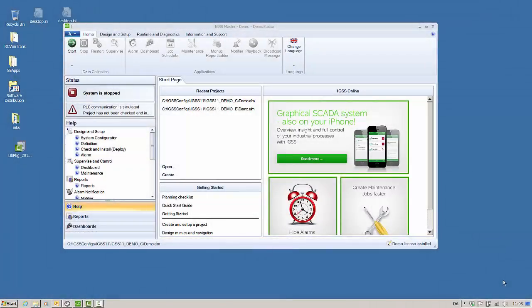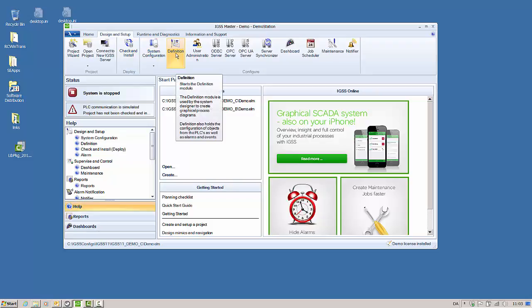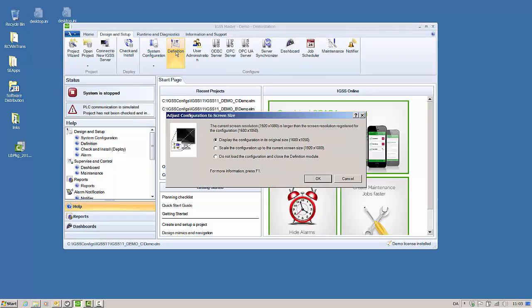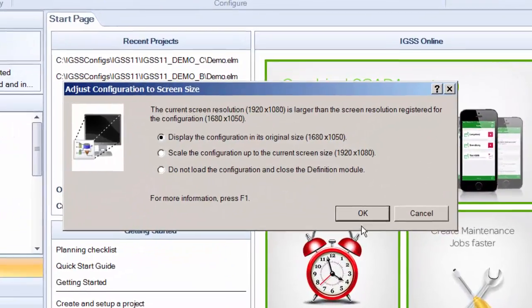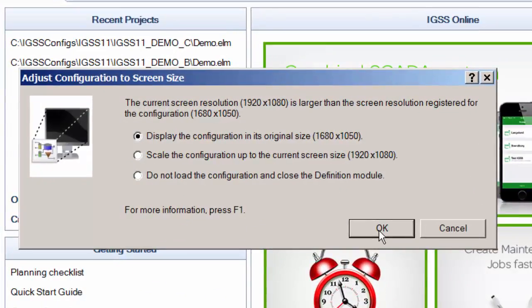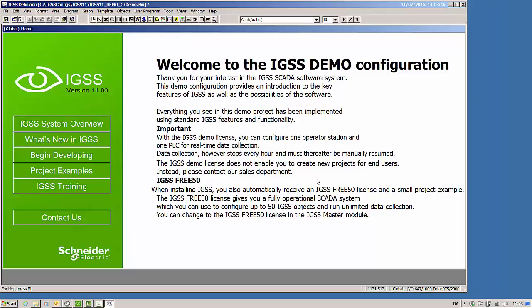IGSS 11 has introduced a new way of scaling configurations when opening them in the definition module. Previously, the system attempted to automatically scale a configuration that was loaded, sometimes with very frustrating results. Now, the system designer will receive a prompt box informing them of a scaling conflict and requesting input about what to do with the configuration. If the resolution of the configuration is different from the present screen resolution, the system designer will be prompted to either close the configuration or rescale it. If the configuration is smaller than the screen, the system designer can load the configuration in its original size, keeping the scale while working, or get the system to automatically scale the configuration up.